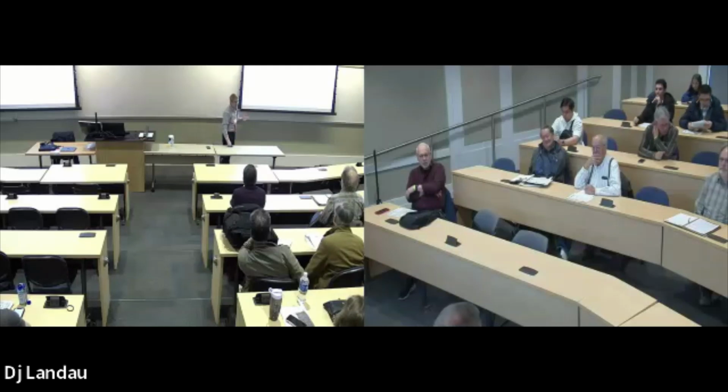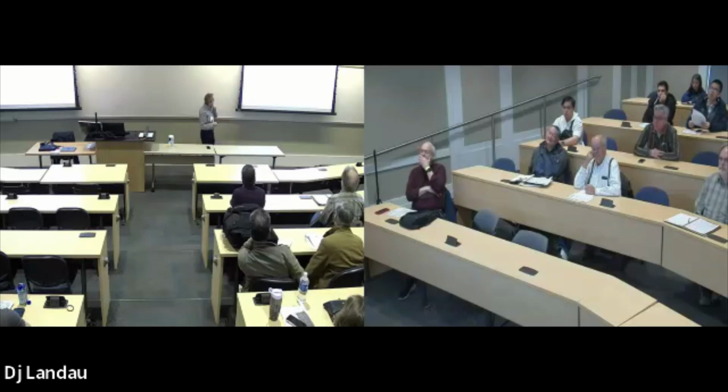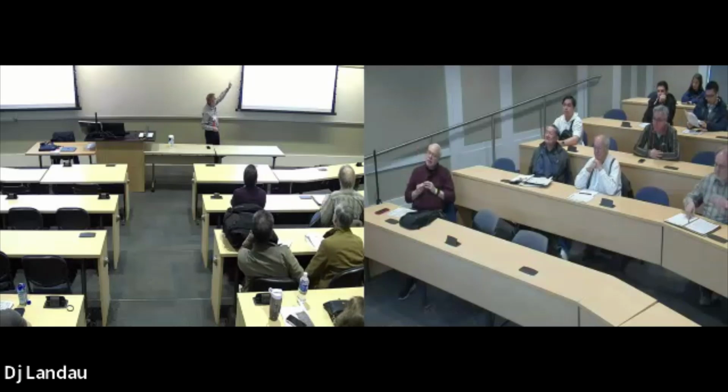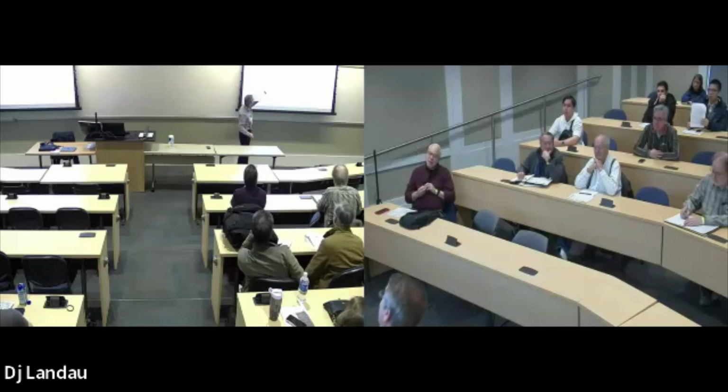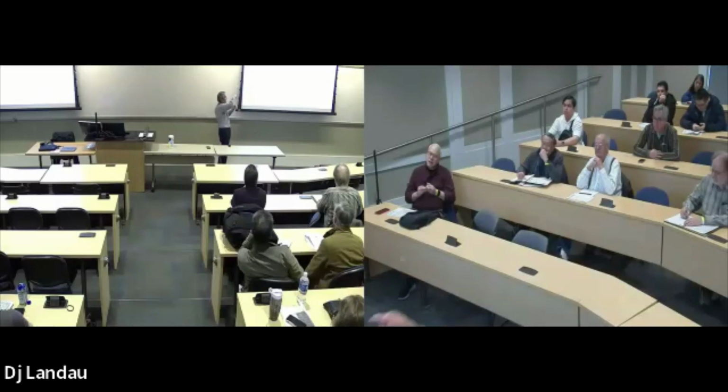Okay. Yeah, excellent questions. All right, let's continue building our grid. Now this is still an isolated system. It's not connected to anything else. We've added a distribution system at the top to serve some customers. Off of this power substation here in the middle, we've built a lower voltage called subtransmission. It's just a lower voltage. It's still a network. It loops around, and it connects to a substation that drops the voltage from, let's say, 69 or 138,000 volts down to 12,000 to 34,000 volts. And then that is what feeds the neighborhoods. So that's what you'll see on the wooden power poles: 12 to 34,000 volts.